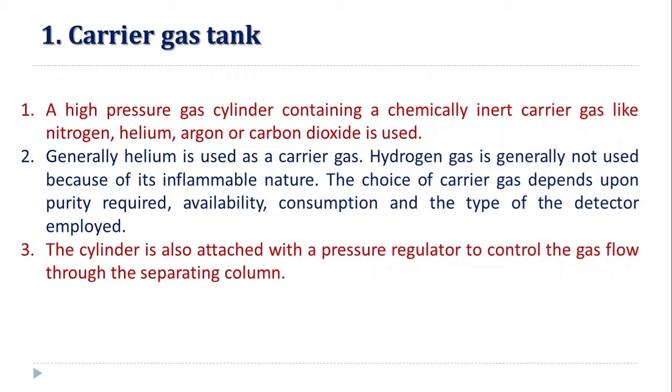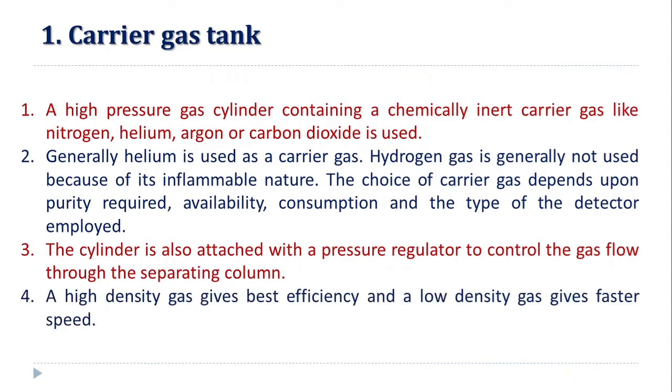It should not be so slow that the solutes present in gaseous or vapor form get condensed. Whatever adsorption, desorption and partition occurs between the mobile phase and the solid phase should be regulated by this gas flow. A high density gas gives the best efficiency, while a low density gas gives faster speed for the analysis. If the density of the carrier gas is high, then the efficiency of the separation will increase, while if the gas density is less, then the analysis will be at a faster rate.